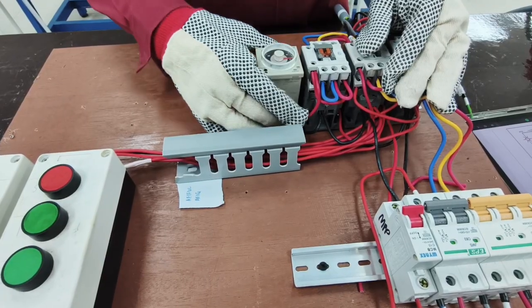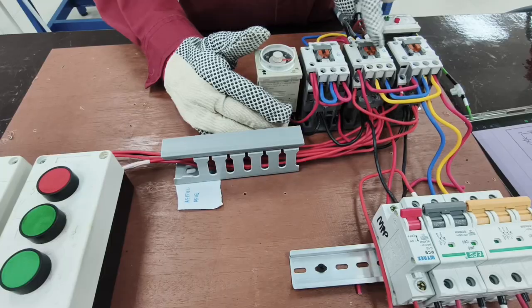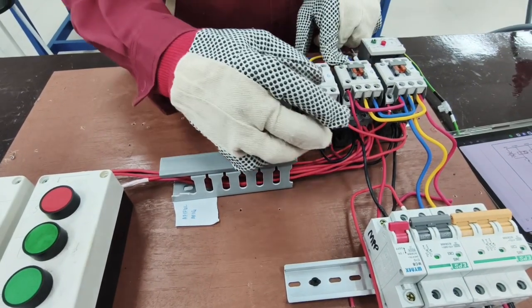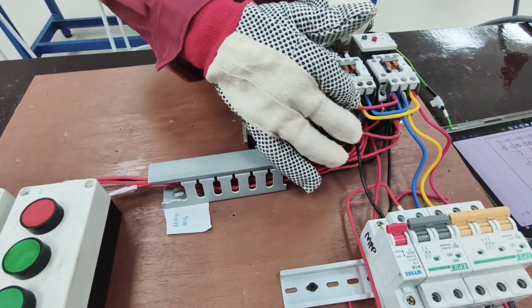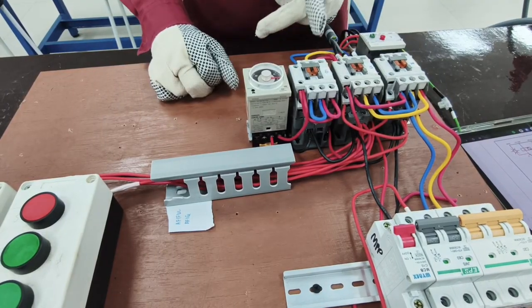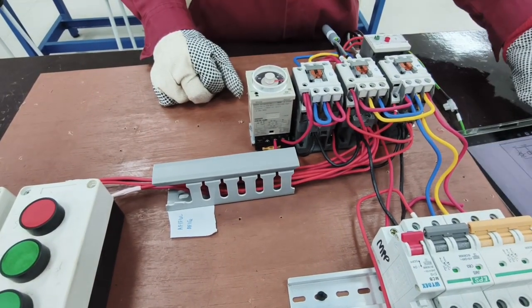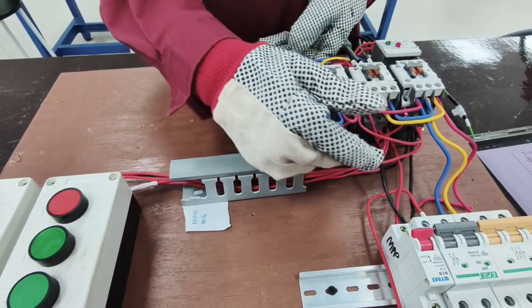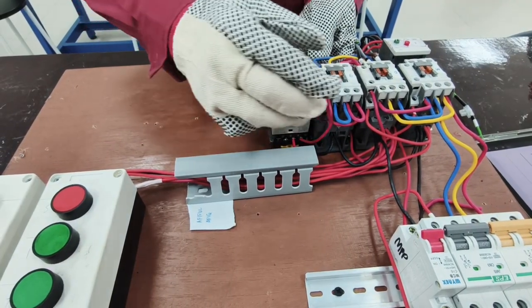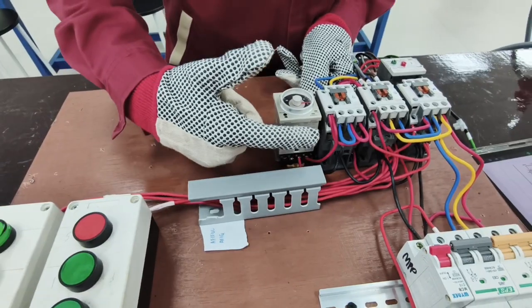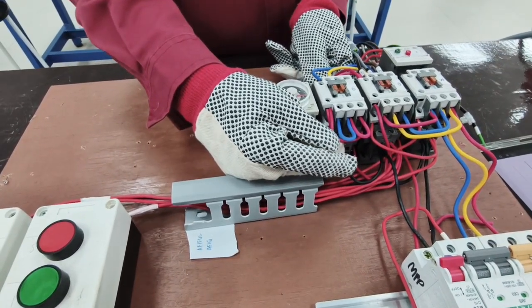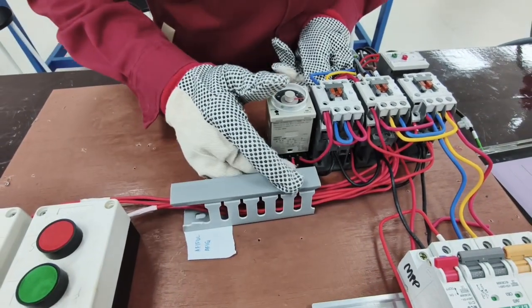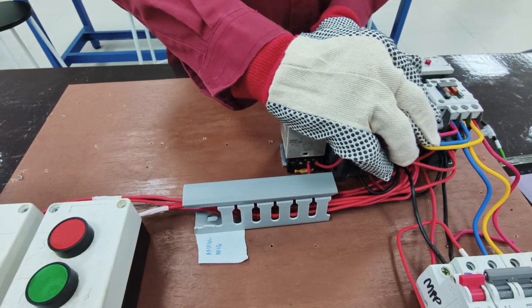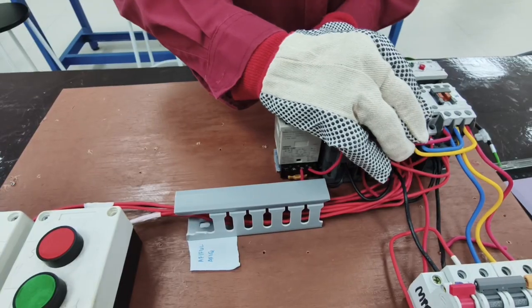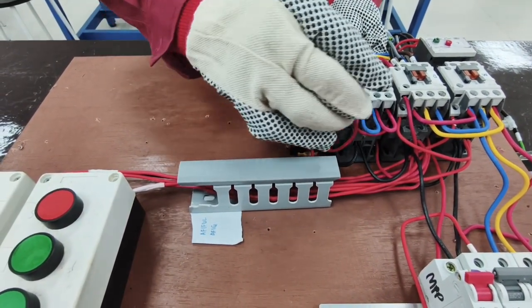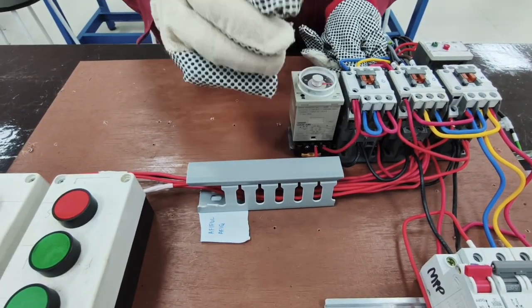So from point number 6, it will go to the interlock mechanism on the delta contactor, but this is the normally closed contact. The normally closed contact is point number 31 for this delta, and from point number 32, it will go to the A point on the star connection, from the star contactor. Okay, and then for this timer, point number 6, we go to point number 5 of the delta contactor, but it will be normally open. This is for latching, because this timer is only triggered once, and we need this contactor latching to hold the instruction and make the current flow.